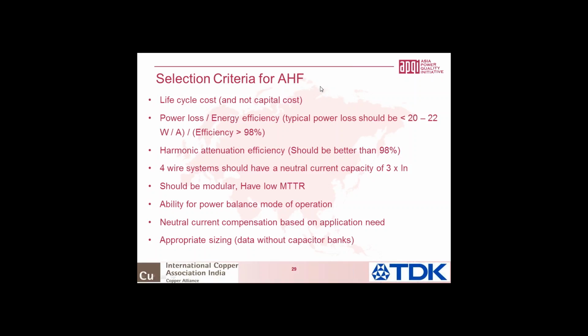My request to regulators and utilities is whenever they are monetizing power factor, either giving an incentive for power factor or a penalty for power factor, it should not be based on just displacement power factor, but it should be based on true power factor, which is the product of displacement and distortion power factor.